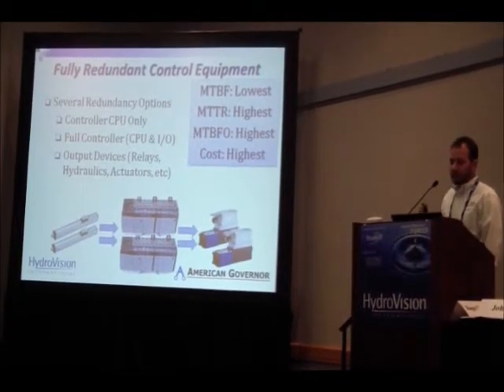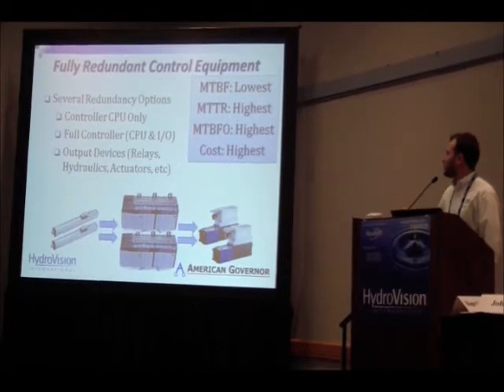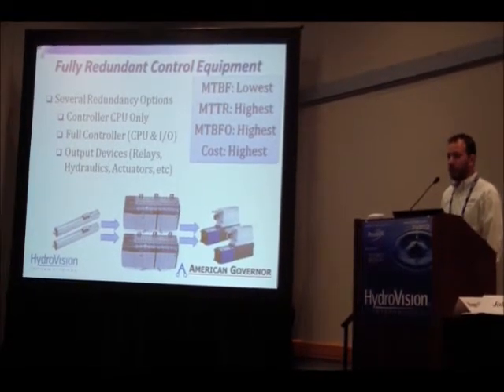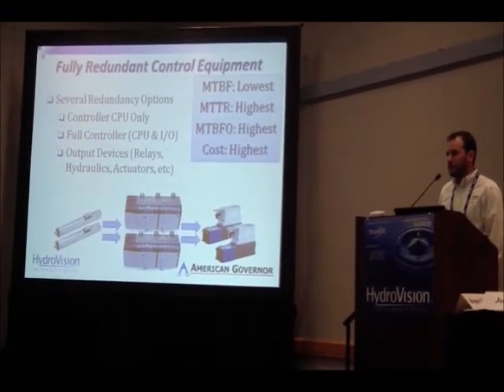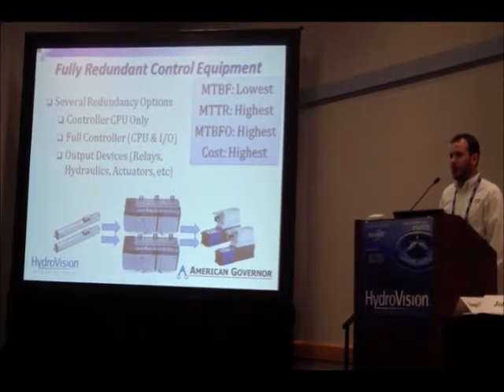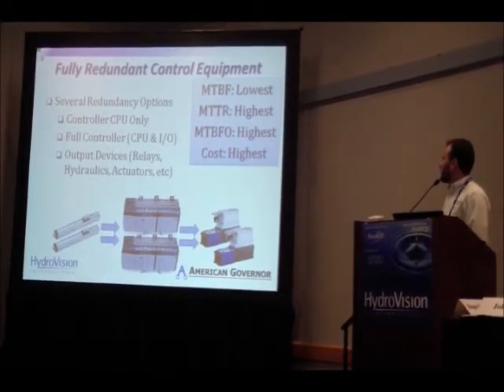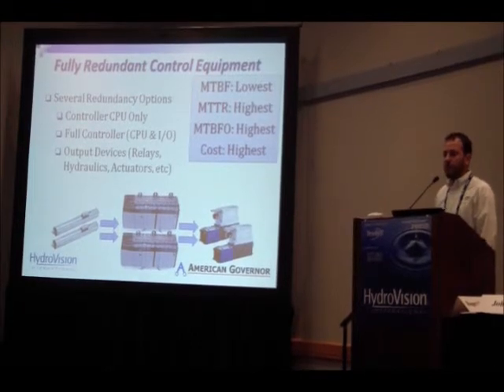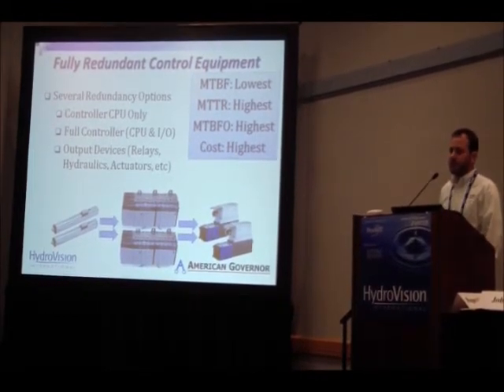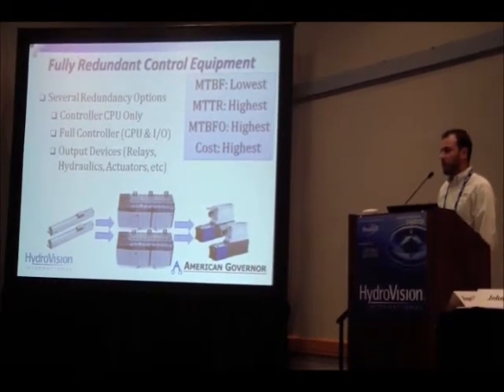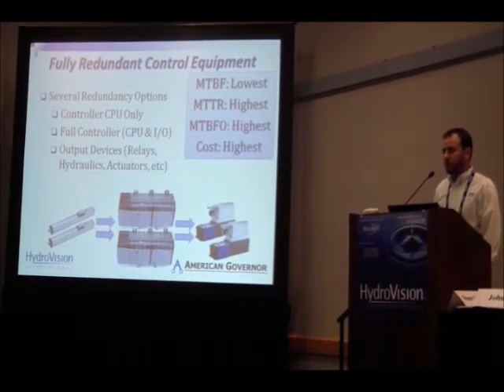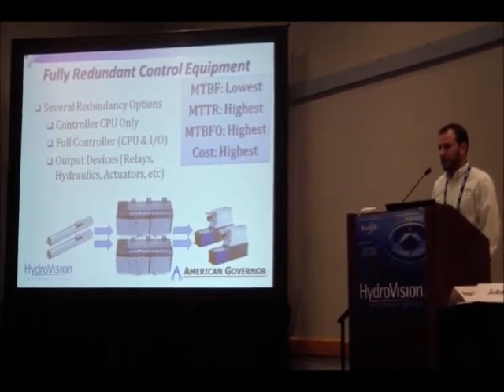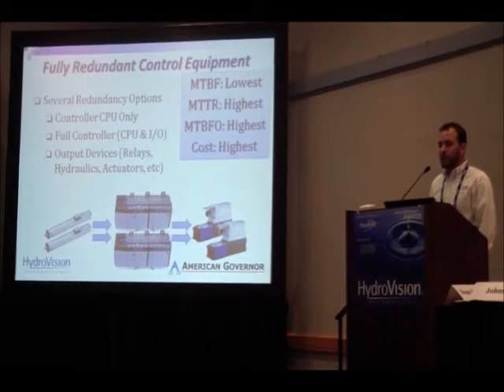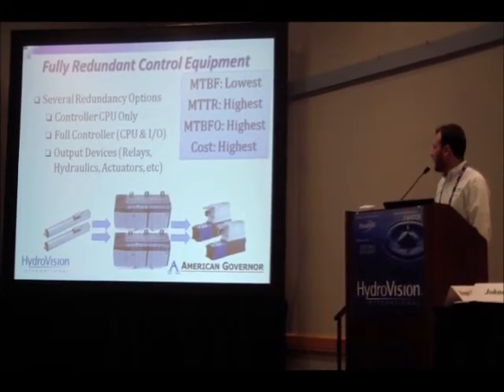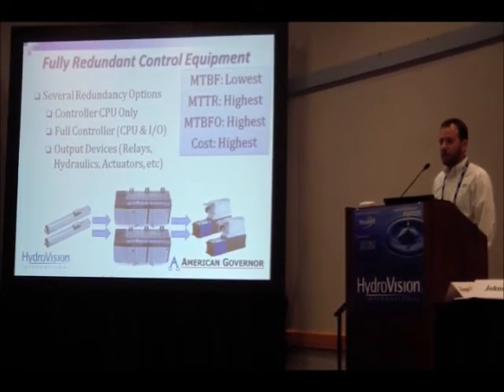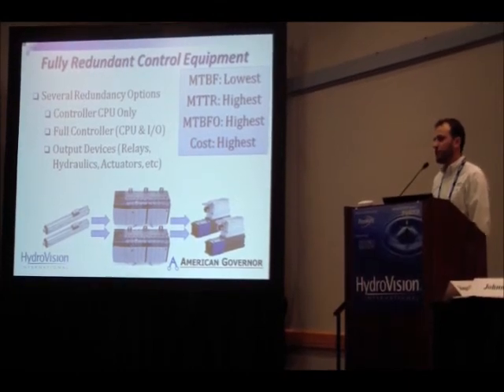These controllers, through the spectrum from the simplest to most advanced, will lower your mean time between failures. Again, same trend. More equipment, the higher probability that you're going to have a failure. It will raise your mean time to repair because your system's getting more complex. But it will also significantly raise your mean time between forced outages because you're striving towards that kind of ambiguous goal of no single point of failure. And your costs will be the highest, not just in equipment costs, but design costs, implementation costs, and maintain costs.